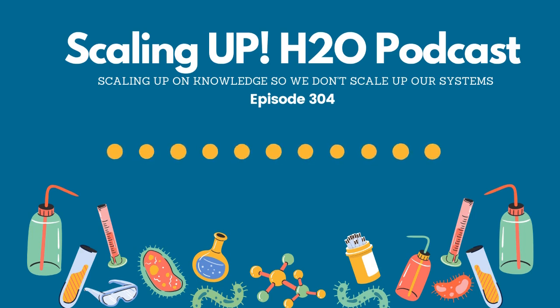Now, do you use corrosion coupons in all systems? Well, if you can, why not? So some people will ask, I've got a chiller or I've got this expensive piece of equipment and I'm using corrosion coupons in that, but then in a closed loop system, I don't use corrosion coupons. Well, folks, if you are treating the water within a system that has metal in it, I'm pretty sure that's every system. If you're not using corrosion coupons, your default is whatever that expensive piece of equipment is that you're treating, that now has become your corrosion coupon. So when that develops a problem, that's your alert that there is a problem in the system.